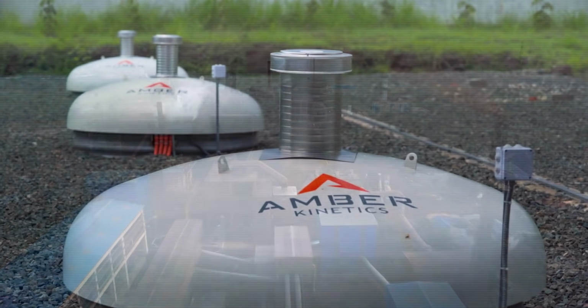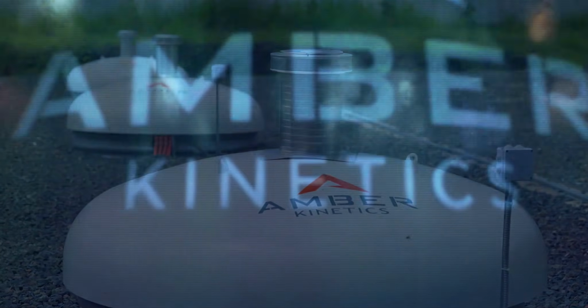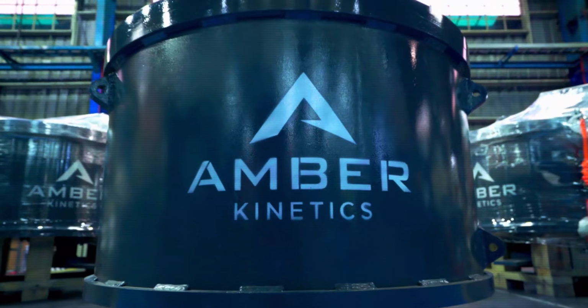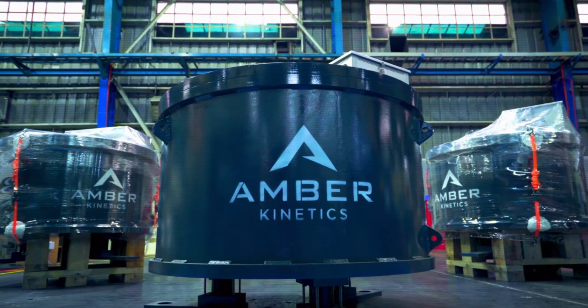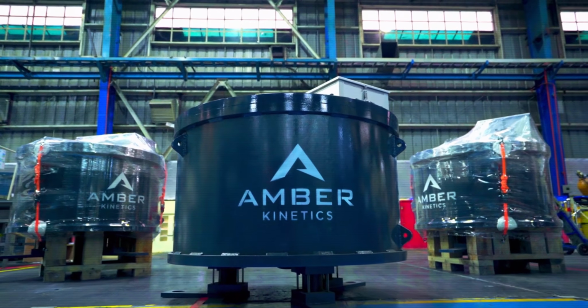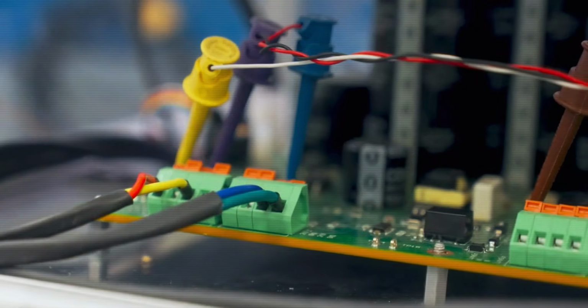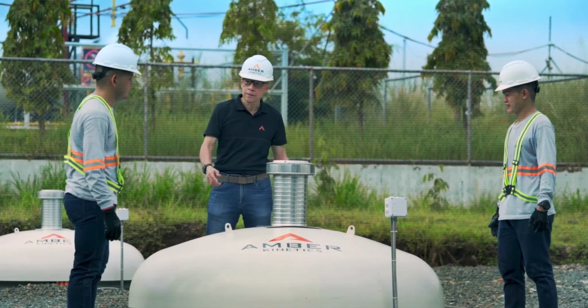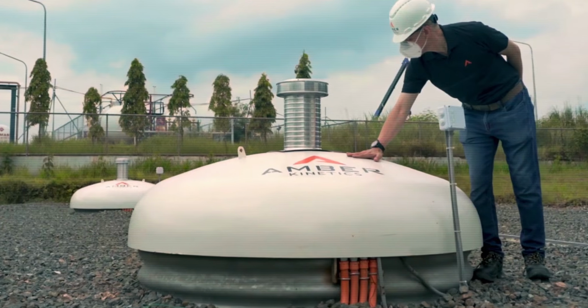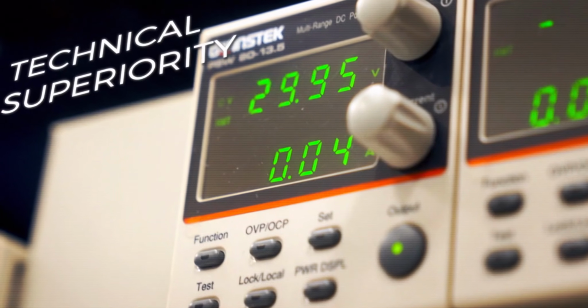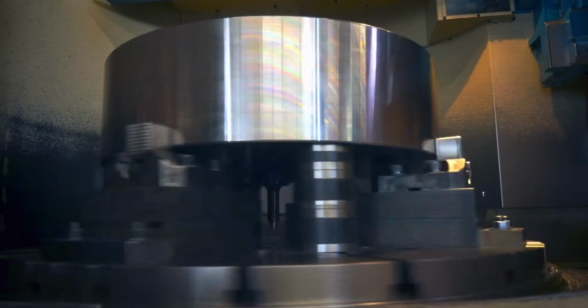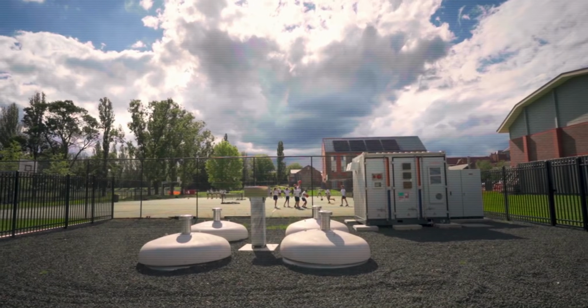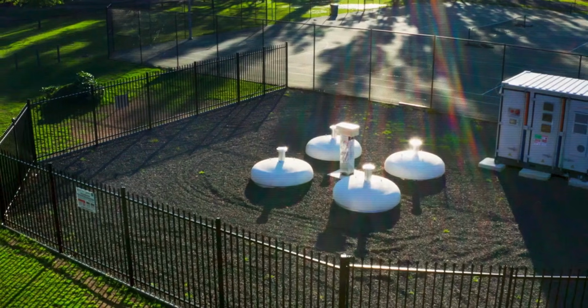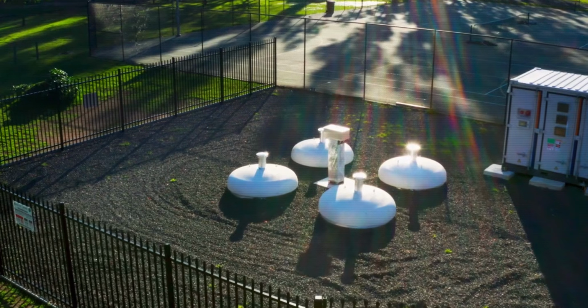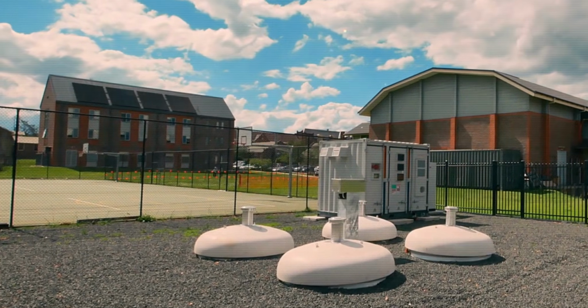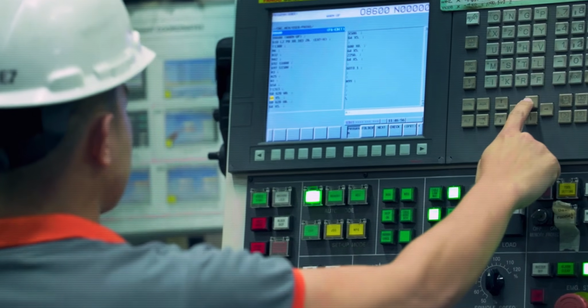None. I modeled a rack of these paired with a commercial rooftop solar array profile, based on a facility that was previously exporting its excess midday generation back to the grid at a fraction of retail value, and then buying that same energy back at full price during the evening peak, which, if you think about it for a second, is a genuinely painful way to run a building. Running that load through the model, shifting stored solar energy into the evening peak using the M32 array, saves this kind of facility approximately $1,850 a month in avoided peak rate purchases.